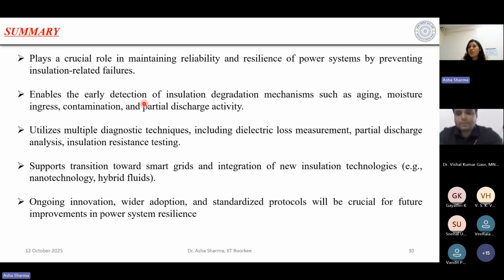It is very crucial, you have to take care of your insulation. It also enables early detection of insulation degradation mechanisms such as aging and moisture. It utilizes multiple diagnostic techniques we've discussed, like dielectric loss, partial discharge, and insulation resistance testing. It also supports transition towards smart grids and integration of new insulation technologies like nanotechnology, nanodielectrics, functionally graded composites, self-healing dielectric materials, and biodegradable materials.